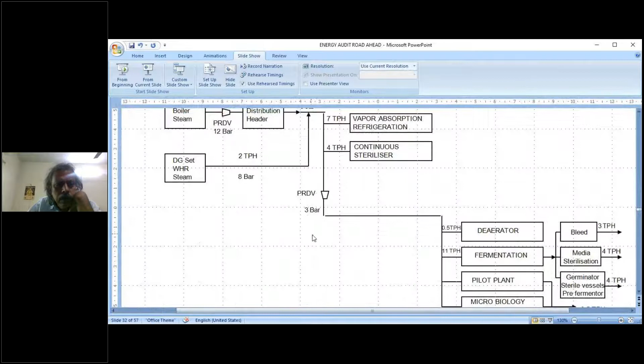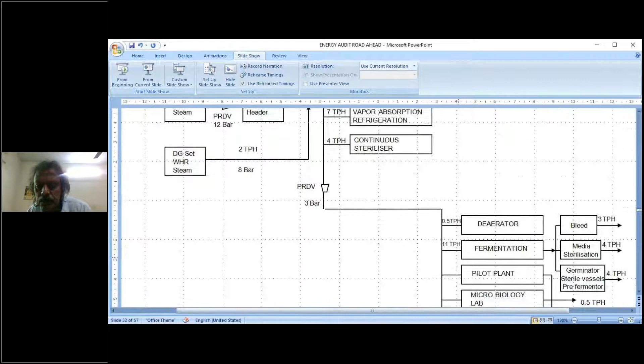So we start the audit by tracing the steam, where all the steam is going, and wherever possible try to quantify the steam for different processes. We may not have meters, so the challenge is how, without meters, we can arrive at a typical steam balance. So we have to go through the basic energy balance route, make a heat balance and find out what will be the requirement here, what will be the requirement here. So at every stage you can find out using this heat balance method, or you can even collect the condensate.